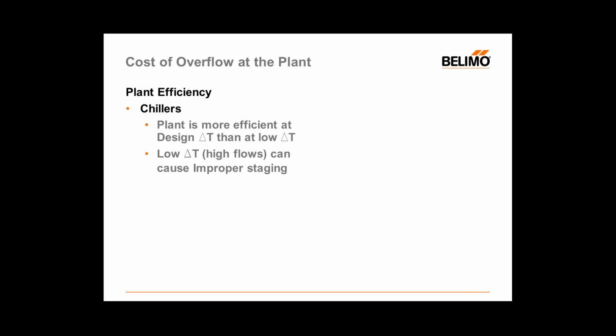So if you give me a 25-year-old screw chiller, I'm going to show you a huge energy penalty for operating it at a low delta T. If you show me a brand new high efficiency chiller that was purchased last week, I'm going to show you that it's much more versatile in terms of its efficiency operation with delta T. And so I don't want to really get into a deep discussion about that, except perhaps on a case-by-case basis. But again, it's going to work better if you give it what it's designed for than if you didn't.